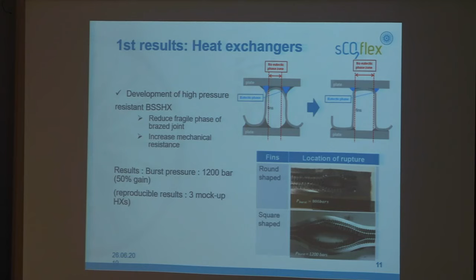For the heat exchanger, which is one of the most important progresses in the project, we developed a very high pressure resistant brazed heat exchanger with increased mechanical resistance compared to the current heat exchangers we know. For example, the current compact heat exchanger will go up to 900 bars, and ours will break at more than 1,200 bars. So we are working within the regulation, the ASME code, and we are more compatible with the current use of this type of exchanger in energy production.